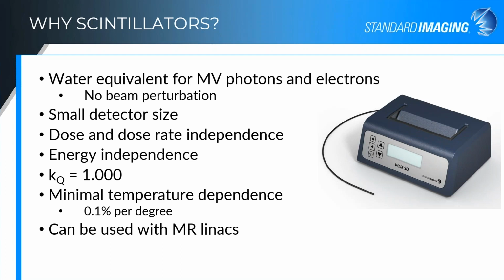They can be made very small. They're dose and dose rate independent for these standard beams. They're energy independent, again, for megavoltage photons and electrons. The beam quality correction factor is unity, and that really reflects that true water equivalence of these detectors. There's a very small amount of temperature dependence. It's about 0.1% per degree, so usually that's ignored for standard QA measurements at room temperature.